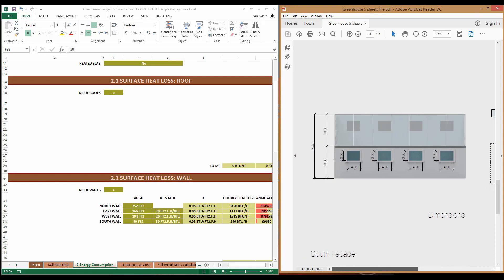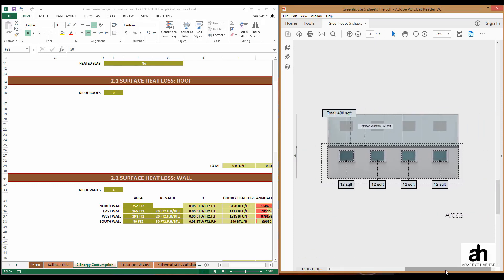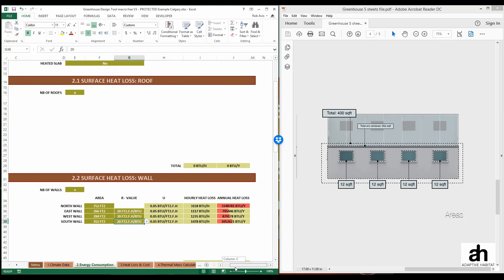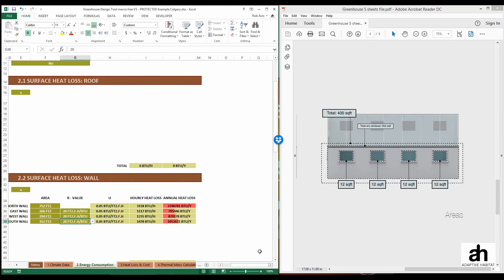Last, we're going to choose the south facade, which has an area of 352 square feet, not including the windows, and we're also going to choose an R value of 20. It should be noted now that we can see where the majority of heat is being lost out of the building with the data visualization on the right-hand side.